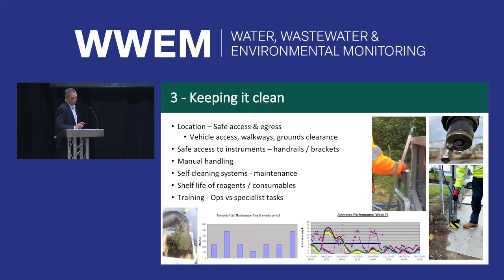Maintenance is the biggest issue we have with instrumentation. I think I said earlier we've got about 55,000 instruments in United Utilities, and a really wide range of maintenance tasks needed on those. We take a different approach based on how critical the instrument is, what site it's on, what it's doing, what it's used for. For the final effluent monitors we talked about earlier, we have a service contract with our partners over at Servitech for 70 of those, and the rest we maintain ourselves.